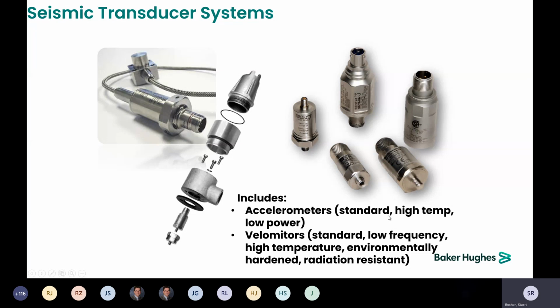We do offer our standard accelerometers, high temp accelerometers, and also low power accelerometers. Velomitors: standard, low frequency, high temperature, environmentally hardened, and radiation resistant. One thing I do want to mention is there are positive voltage sensors and negative voltage sensors. The positive voltage sensors will work with a negative voltage system, and the negative voltage sensors will work with a positive voltage system, but the signal will be 180 degrees out of phase. So you need to be aware of the polarity of your signal, and you can build a small electronic circuit to invert that polarity if needed.